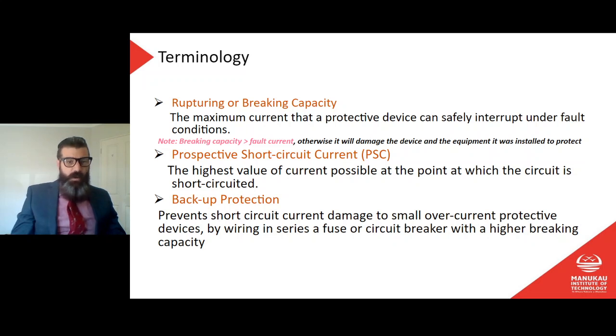Okay. So I guess then you could say that if I had a 20 amp circuit breaker and it had a maximum breaking capacity of 6,000 amps, but I had a prospective short circuit current of 7,000 amps, well, what am I going to do? Well, if my backup protection, if my next fuse back in the circuit has a breaking capacity of 10,000 amps, well then that's going to be fine in that situation. That one will switch off. My first circuit breaker, the small one, might not trip, but the backup protection will. So at least then we should be safe.